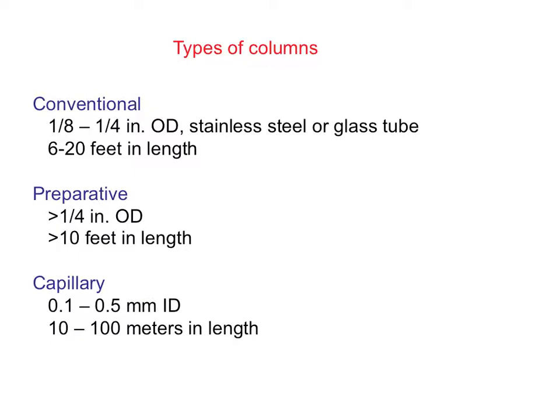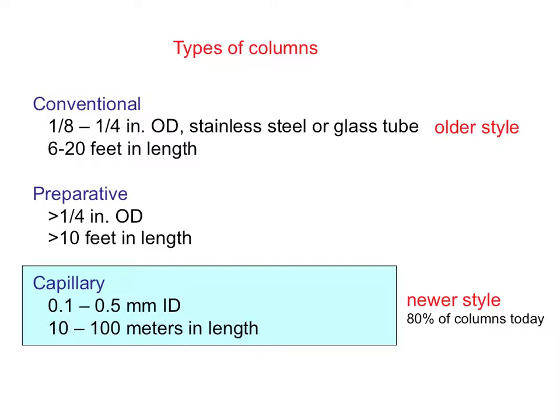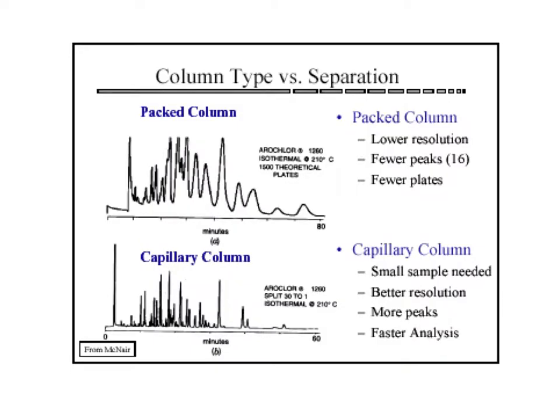Other than the preparative columns, which are used to separate large samples, there are two types of columns in common use. The conventional or packed column is an older style column. Capillary columns give much better separation and are found in most higher-end instruments. This slide shows the difference in separation between the two types of columns. Note that the packed column leads to broader, overlapping peaks. Two compounds that elute close together may be mistaken for a single compound and appear as one broad peak. The capillary column has resolved the mixture into many more clearly defined components.